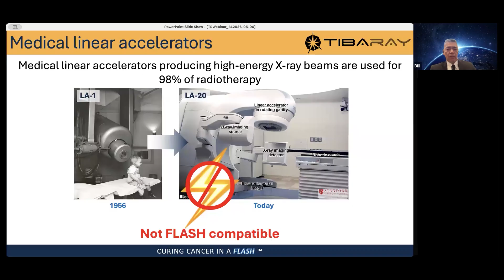But the challenge is that these existing medical linear accelerator X-ray based systems are not flash compatible, because you can't just turn up the dial on them. They're already operating at essentially the maximum of the current technology. And so we need something hundreds of times faster, and that requires totally new technology.